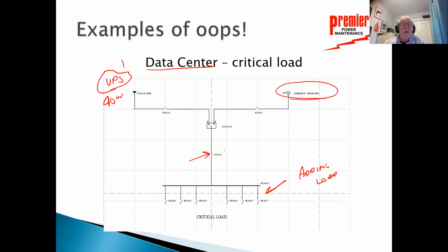It's one of the situations where this breaker should have been designed to trip after these two breakers tripped. This is the last thing in the world you want to trip. You only want it to trip before you damage the switchgear itself. To my way of thinking, if I'd have been designing that, I'd have put a piece of copper bus in there and let the other two breakers go. But it's just another example of, you know what, we think that we have a solid system here that nothing could possibly go wrong with, and yet it can. It can.